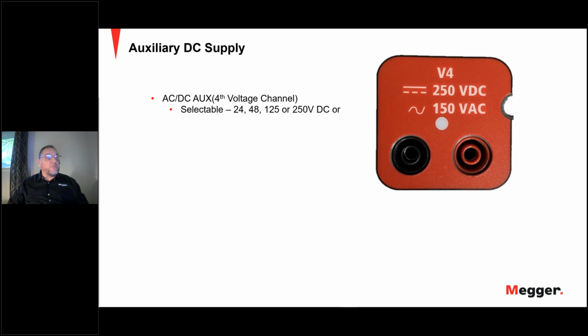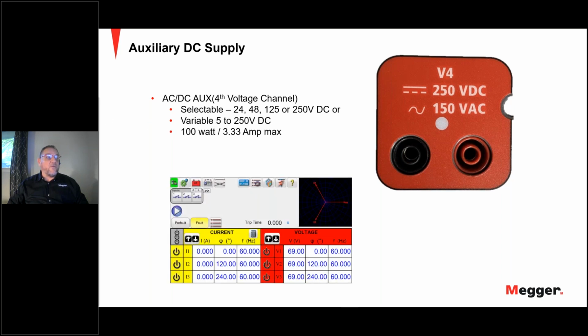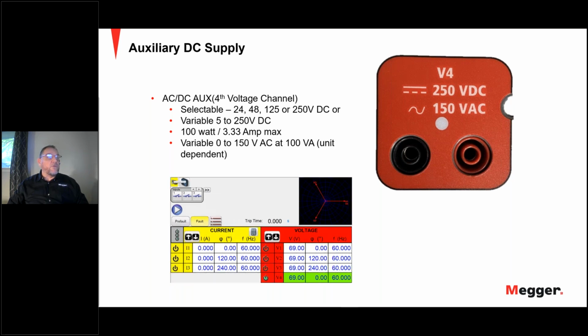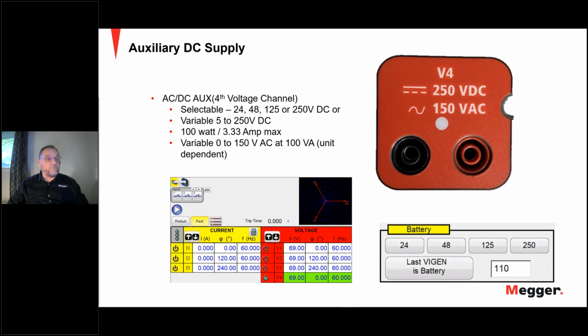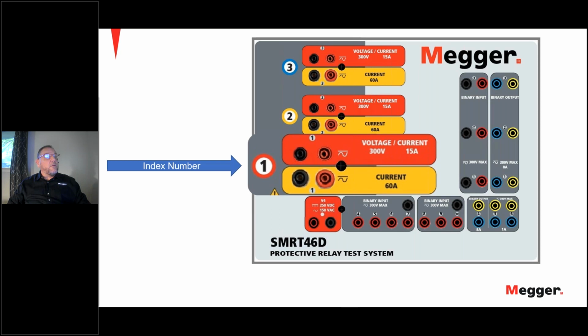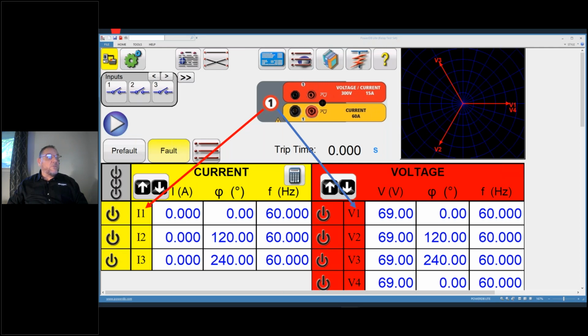Like I mentioned, you've got selectable values of 24, 48, 125, and 250 volt DC, or it's variable, anything from 5 to 250 volt DC. It's got an output capability of 100 watts or 3.3 amps, so it can really power up quite a substantial relay with backup supply as well. And then, of course, the variable AC voltage of 0 to 150 volts, 100 VA. And as I mentioned there, it's unit dependent. There's just an image showing the different selections that can be made with the voltage. Okay, so moving on. On the side of the Vigens, you'll have an index number, and this index number actually references which channel you are talking about. So in this case, channel number 1.